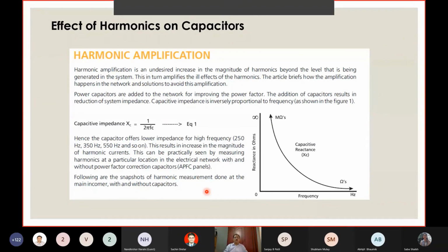So we need to address this capacitive impedance, which causes the plain capacitors to become a low impedance path in a network. See, typically, if you look at the harmonic, the voltage harmonic is spreading parallel circuit. Current harmonic goes from where it is generated towards the grid. The line of its process is through the cable to bus bar to switches to transformer to the grid.